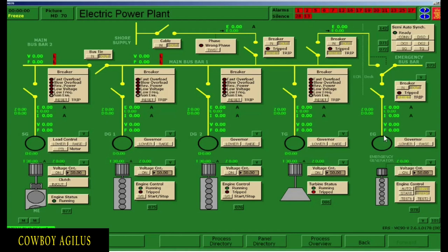So if you start the generator and come here to number 70, check for the output voltage in letter V. There should be a 440 volts reading here. If you do not see a 440 volts reading, go down to voltage control and click on — the 440 volts will appear. Then connect the breaker by clicking breaker in. After that, go back down to the engine control and click auto. Do not forget to put your emergency generator switchboard in automatic mode.